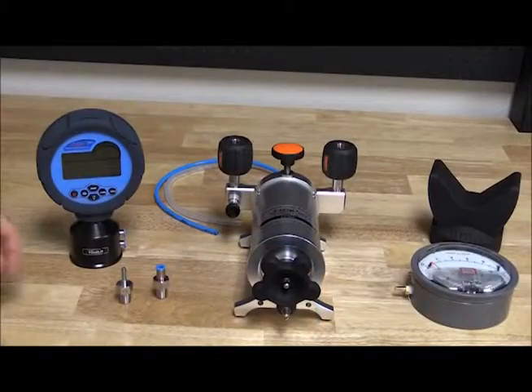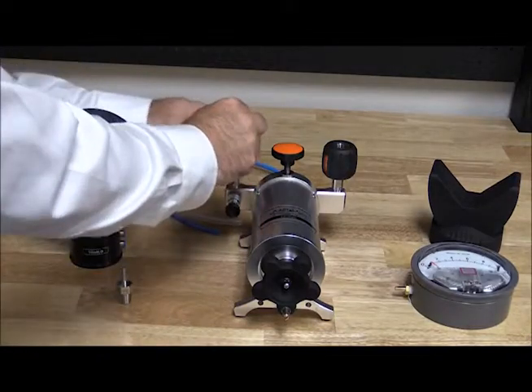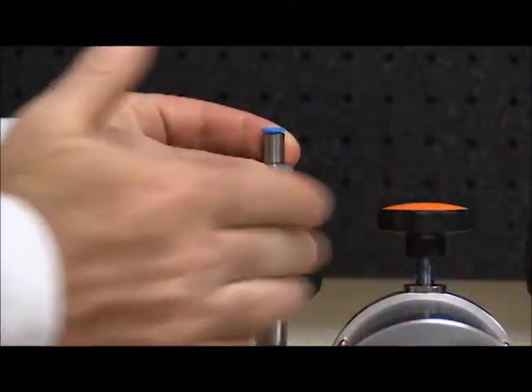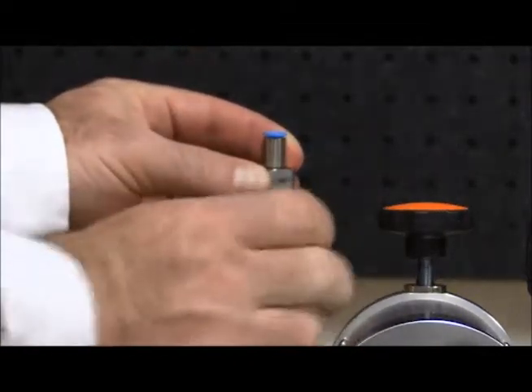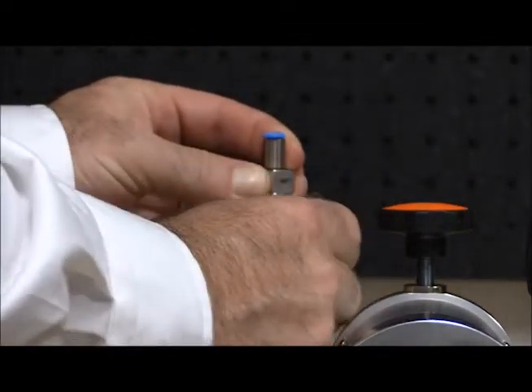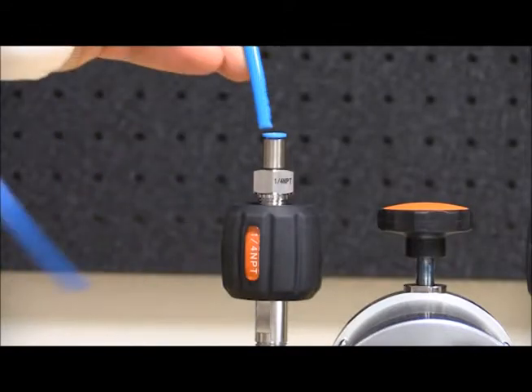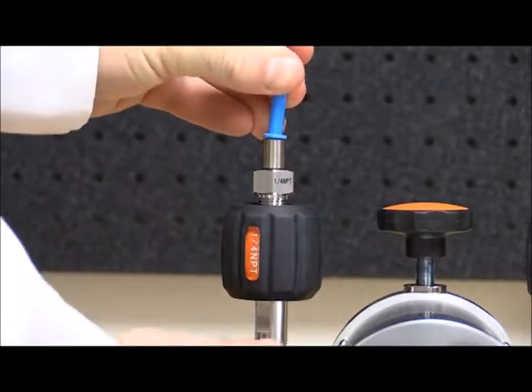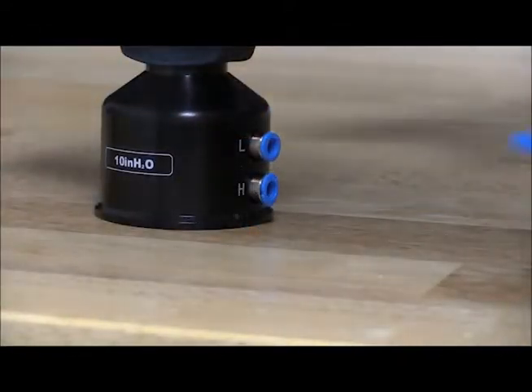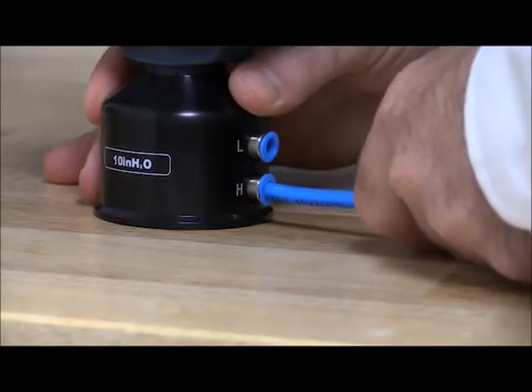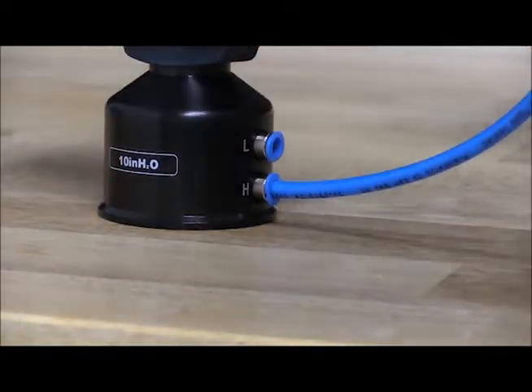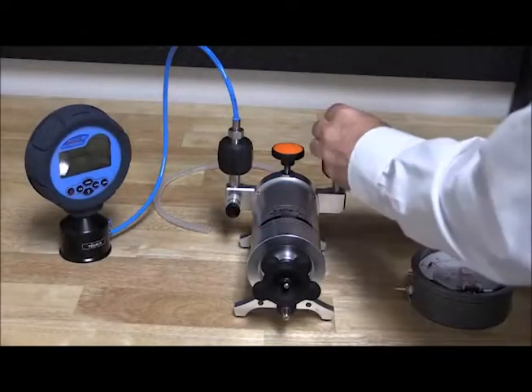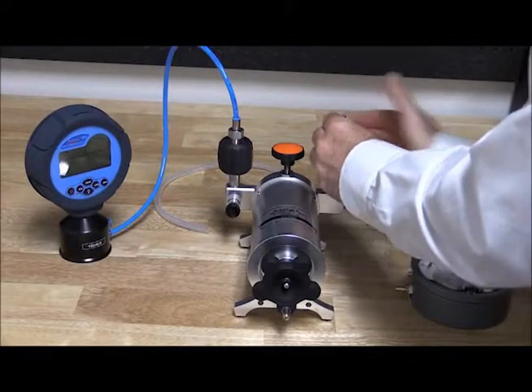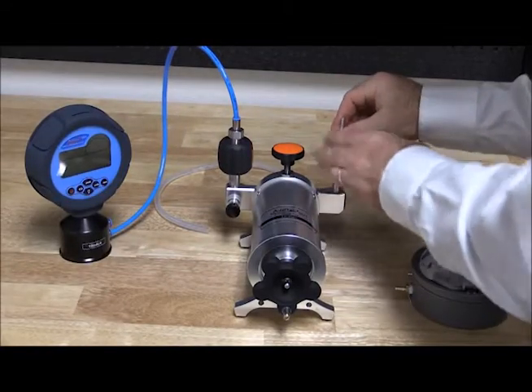For this method, we will connect the high ports for both the reference and the device under test, or DUT, to the 901 pump, leaving both low ports open to atmosphere. Most all Additel pumps come with easy-to-use hand-tight quick connectors that do not require the use of PTFE tape or wrenches. The Additel 681 differential pressure gauges also connect with easy-to-use quick connectors.